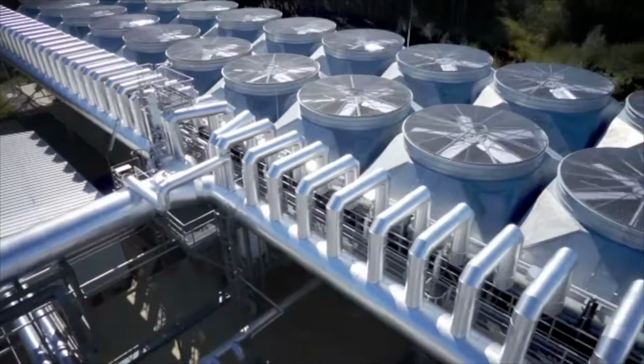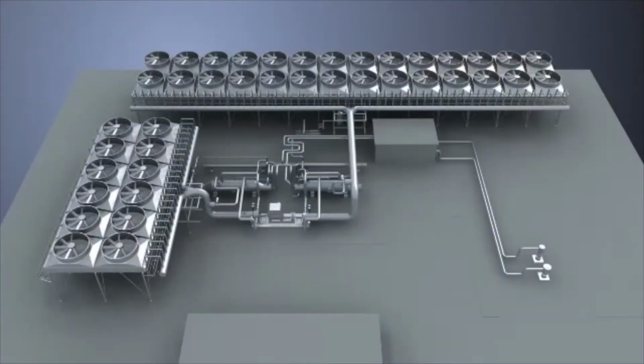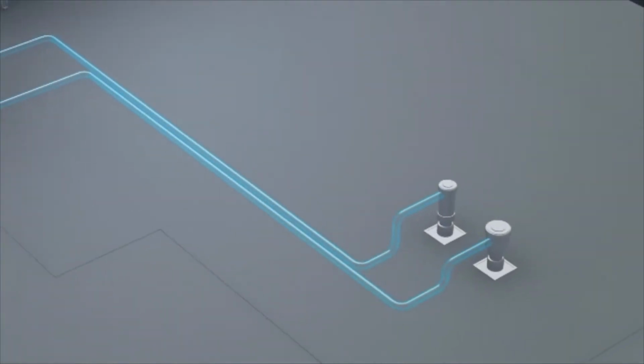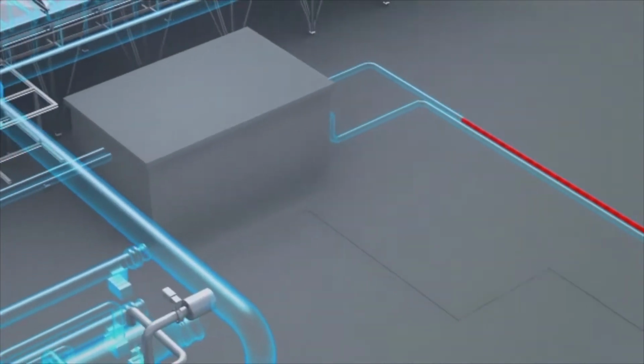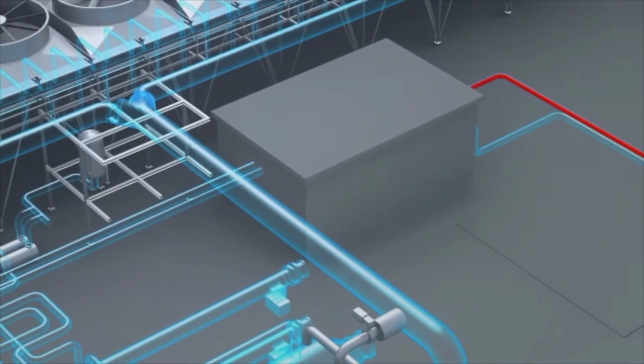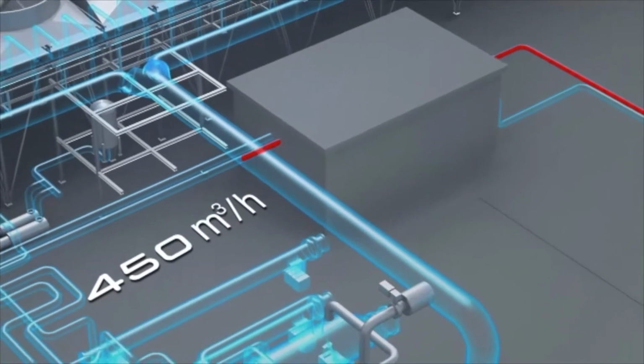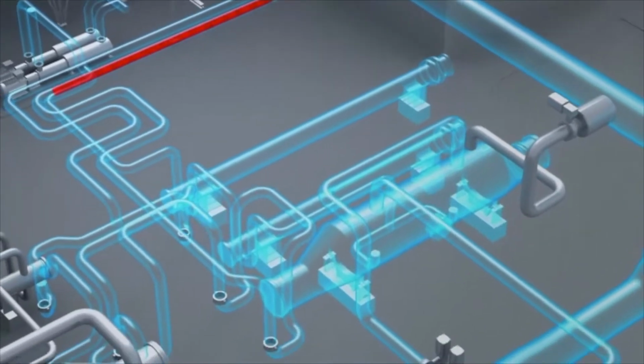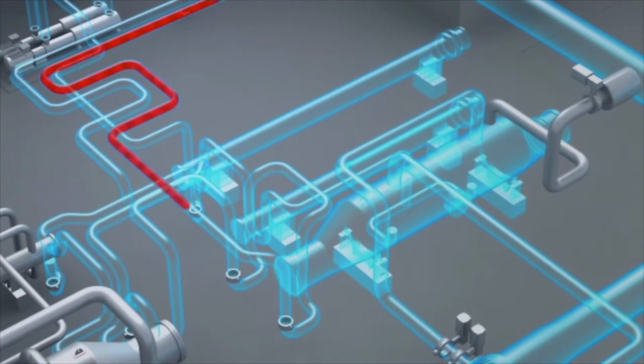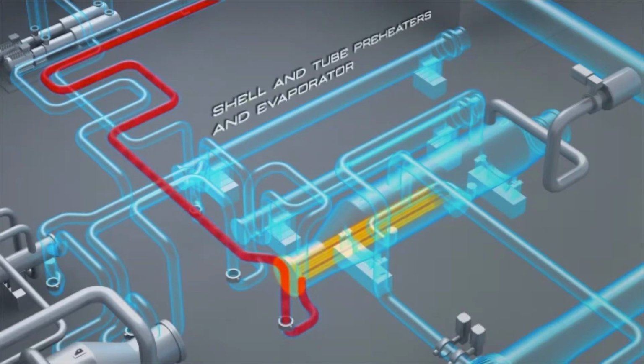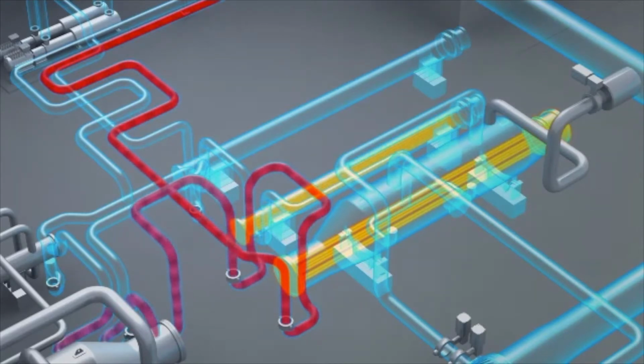Let's take a closer look at the route followed by the geothermal water within the process. A submersible pump pressurizes the water in the production well to feed the ORC cycle at a temperature of 140 degrees Celsius with a flow rate of 450 cubic meters per hour. The pipelines of the balance of plant carry the geothermal water, after appropriate filtering, to the heat exchanger of the ORC plant. The water passes first inside the tubes of the evaporator, then inside the preheaters, transferring its thermal energy to the working fluid that is contained inside the pressurized shell.